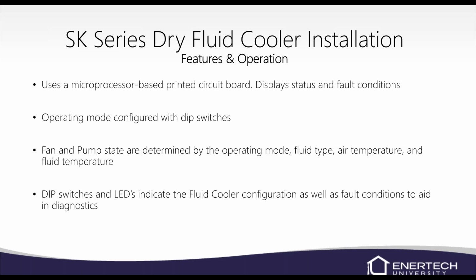It uses a microprocessor-based printed circuit board, and it will display status and fault conditions. In order to configure the operating mode that you want to choose, there are some dip switches, and we'll talk about those here in just a second. The fan and the pump for the fluid cooler are determined by the operating mode, the fluid type, air temperature, and fluid temperature. So it looks at quite a bit of things and decides when it needs to run the pump or the fan. Again, dip switches and the LEDs indicate the configuration as well as the fault condition to aid in your diagnostics of the unit itself.